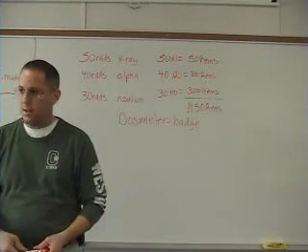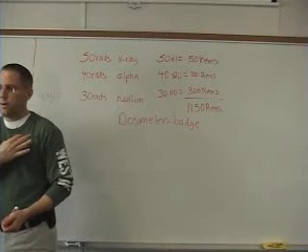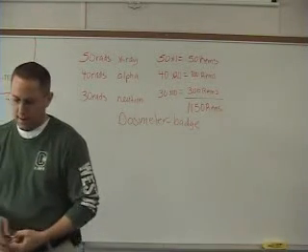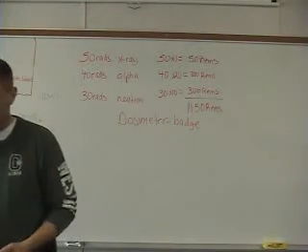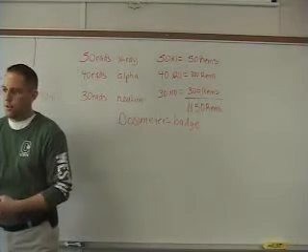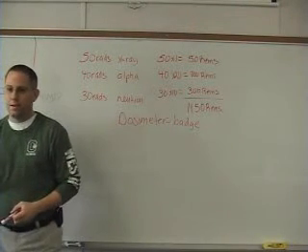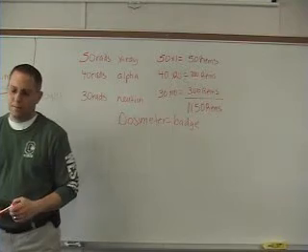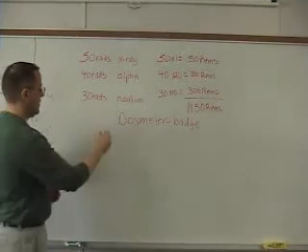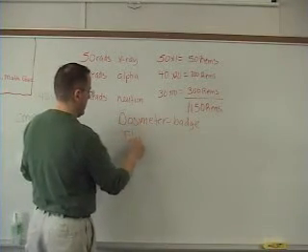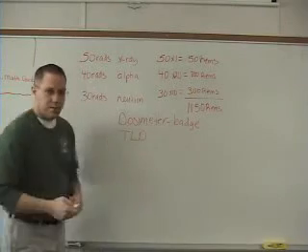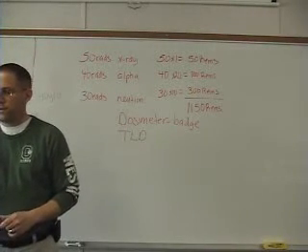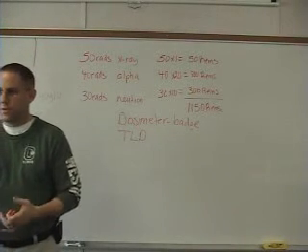On page 60, 61, and 62, you have the film dosimeter, the TLD, and then there's one called the self-reading pocket dosimeter. The film dosimeter is a little badge that inside of it has a piece of x-ray film. They measure how that x-ray film changes over time, and that will give an indication of how many rems you're exposed to if you've been exposed to anything. There's another one called a TLD. It looks pretty similar to the film badge, but it has a crystal inside of it. So that crystal will change with exposure to radiation.